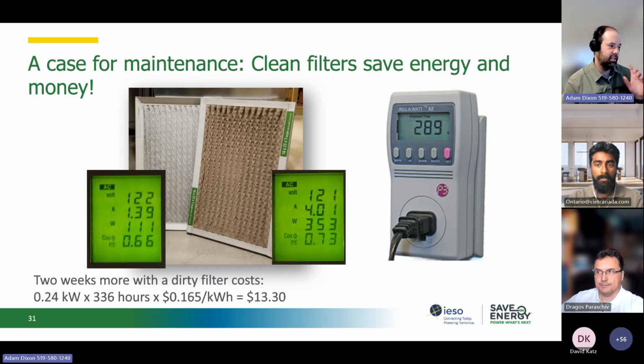Maintenance is always important. This example is not a school board, it's actually in my house. With my furnace, a clean filter on the left, we monitored it running at 111 watts. A dirty filter was running at up to 353 watts, and this is with a high efficiency multi-stage fan, so it works harder to get the required airflow. If you have a single stage fan, it won't necessarily cost more in demand, but the fan will run longer to push air through the dirty filter. The effects will be the same depending on your situation.